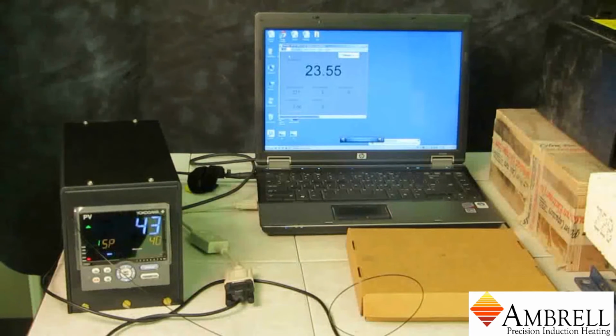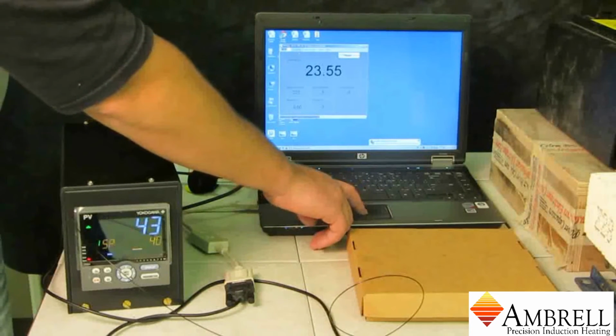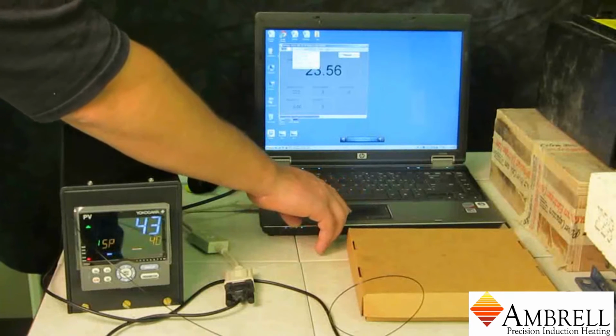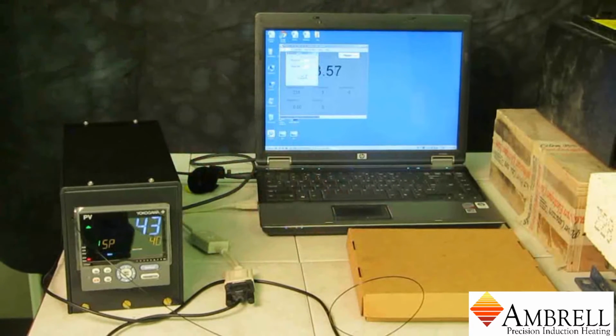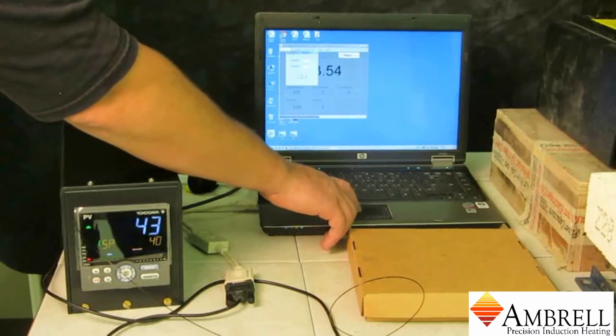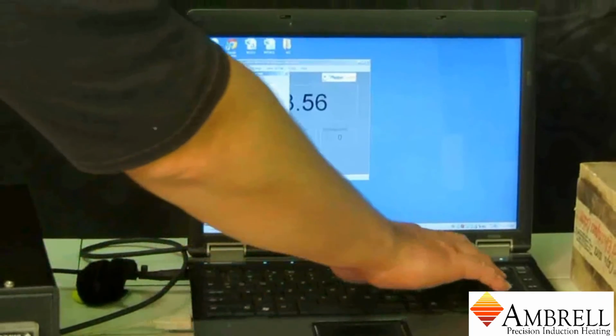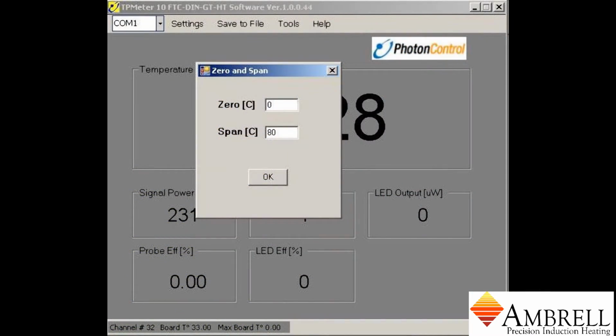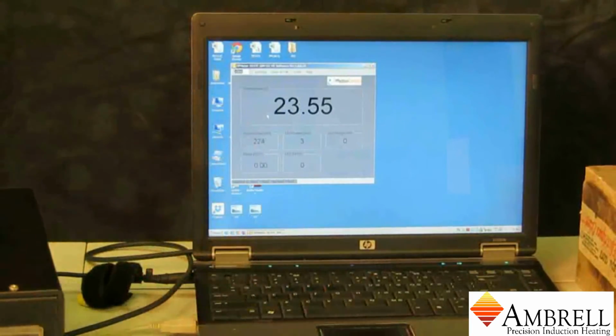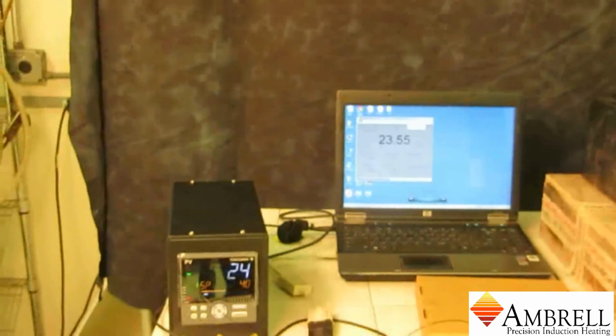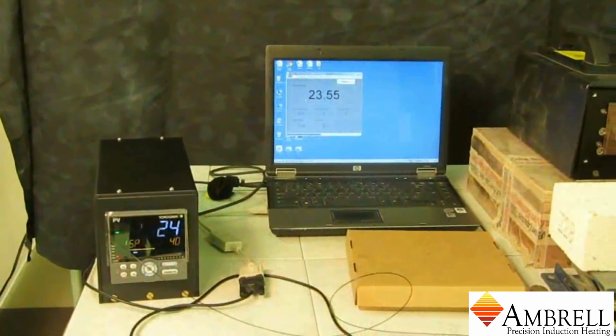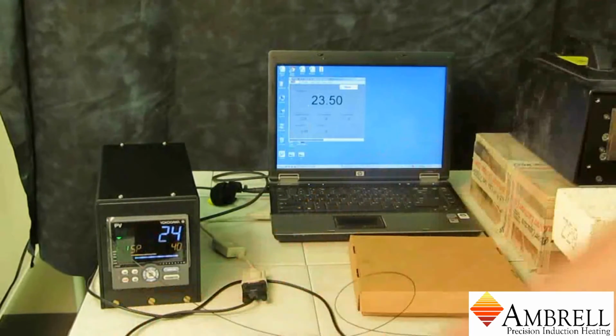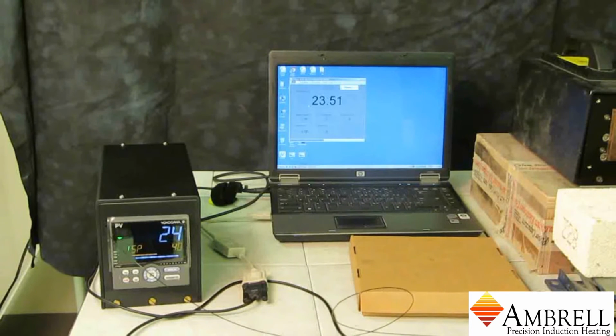So, in order to fix it, we'll go through the Help menu, log in once again, type the password, click on the Settings menu, and select 0 and Span. So this needs to say 0 is 0, and the span is 80. Alright, this will properly rescale the Photon control analog output. Now you can see they are both reading the same value of 24 degrees Celsius. Alright, so what we've done is change it from manual to automatic mode.